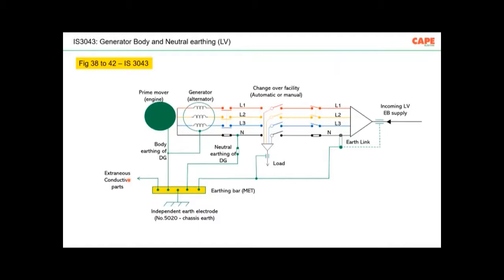As I said, earthing is a very, very important subject. If earthing is wrong, or if you make a mistake in your earthing, the building can create a very dangerous situation. But you must also understand that an electrical installation will work without an earthing as well. Then what is the purpose of earthing? Earthing is to ensure that your installation is safe during an insulation failure, or during a surge, or during a lightning, or during some events. So in a normal condition, your electrical installation will work even without earthing. So whatever we are doing in the name of earthing is required only when there is a critical situation.